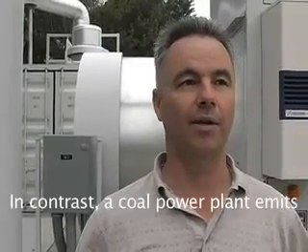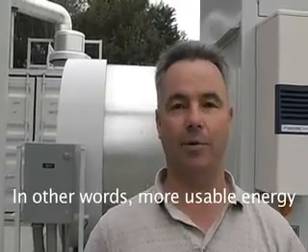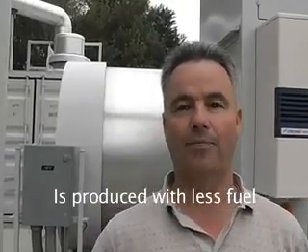The exhaust that comes out of these is almost entirely just CO2 and water, and we could use landfill gas to feed these if we could get some here. Compared to coal-fired power plants, this is considerably more efficient. We are about 43% efficient just on the electrical side, and we end up about 80% efficient by the time we use the heat recovery as well. Coal-fired power plants are about 33% efficient, so we have much better efficiency for the amount of exhaust we produce.